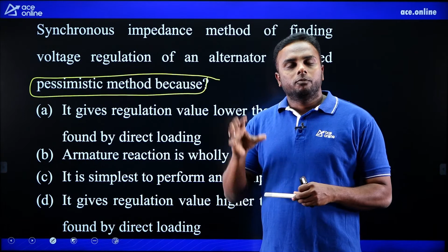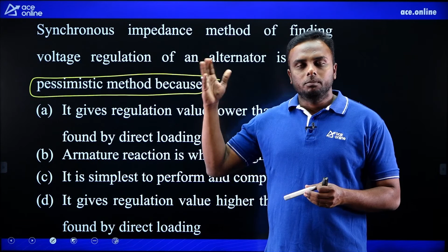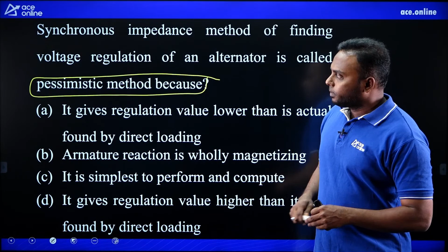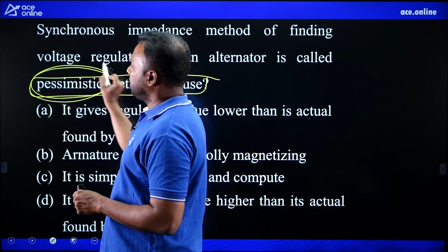But if you find the same regulation using the MMF method, we'll get less than 25%, say 20% - the lowest we get. The synchronous impedance method gives the highest value, 30% in this example. Because of that, we call the synchronous impedance method pessimistic, since it gives voltage regulation more than the actual voltage regulation.